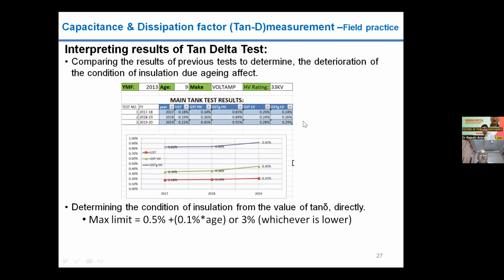As per guidelines, if you look into the different standards, on a new transformer the result may be 0.5% initially, and variation is allowed according to age at 0.1% per year. So for a 10-year-old transformer, 10 into 0.1 means 1%, and with the initial value of 0.5%, the tan delta value may be 1.5%. Accordingly, every testing engineer, by virtue of his or her experience, may look into these results.